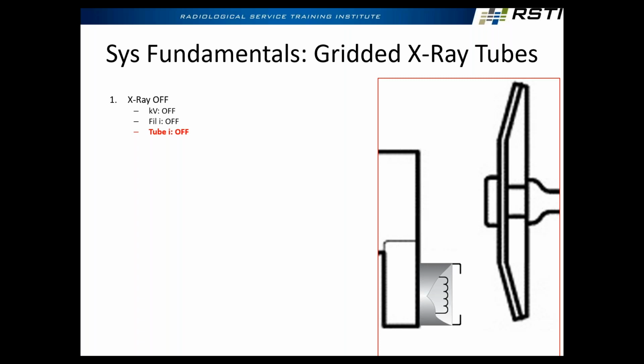But this example number 1, if you have no KV and no filament current, you can't have tube current. That makes sense, everybody? I have no KV here. I have no filament current. There's nothing going across here. No radiation being produced. This next example, I have KV off, filament current on. How much radiation is being produced? None. There's still no tube current. There's nothing to suck it across there. So I have filament current here. I have no KV, and I therefore have no MA.